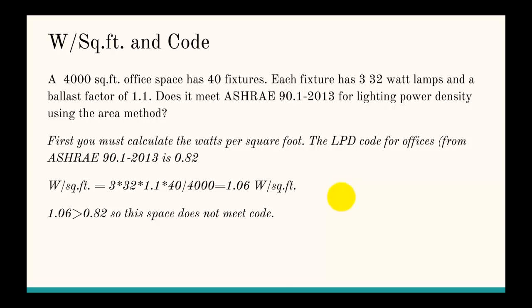We calculate watts per square foot by taking the number of lamps per fixture times the wattage times the ballast factor. So 3 times 32 times 1.1 is the power usage in watts for one fixture. Then we multiply by 40 fixtures and divide by 4,000 square feet to get 1.06 watts per square foot.